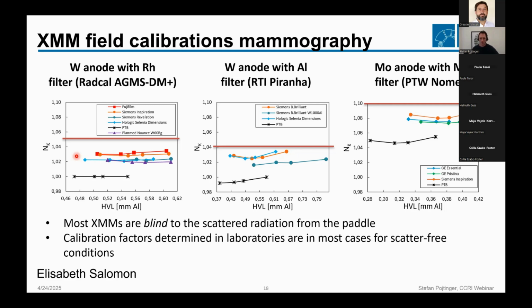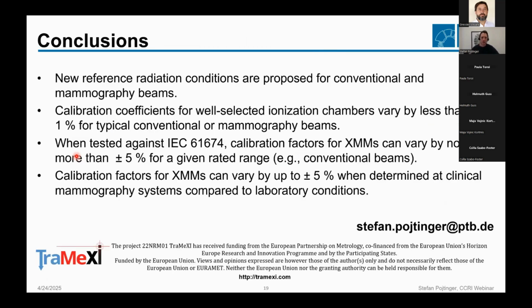But of course, that cannot work for all mammography devices in existence, because your scattered radiation will always be a little bit different depending on the device and the phantom you are looking at. So if you really want to measure the scattered radiation, you have to think a little bit more about it if you want to do it with, let's say, low uncertainties. This brings me to my conclusions.